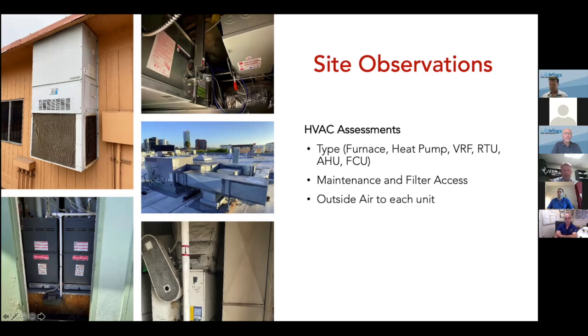Those portable classroom units typically have pretty poor filtering and not a lot of outside air, and we found a lot of issues that need to be resolved, like maintenance and filter access. The photo on the upper right shows the filter access, with the disconnect mounted right in front of it, so every time they need to change a filter, the disconnect has to be removed, dropped down, the filter changed, and put back up. That's one thing that'd be very easily fixed by extending the wiring to the disconnect to allow that filter access.